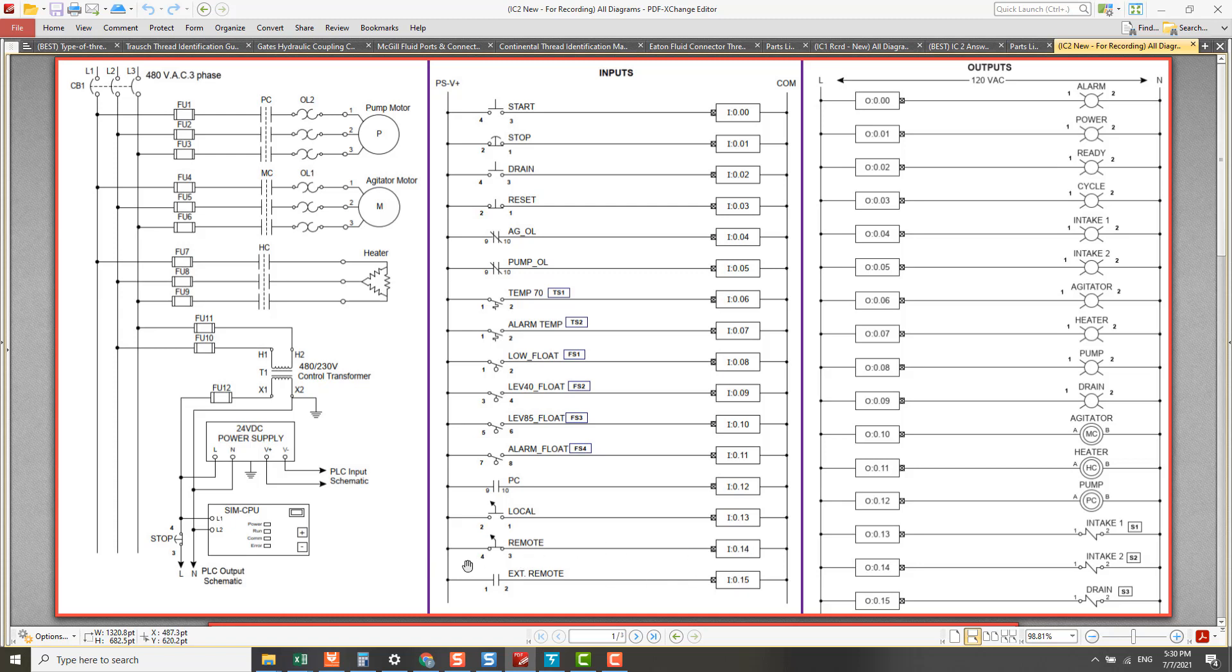This is a remote switch. It is normally closed. When we switch the switch to local, this remote switch will change from normally closed to open. So when it opens, there's no current flow through this path to energize this PLC input channel load at channel 14.